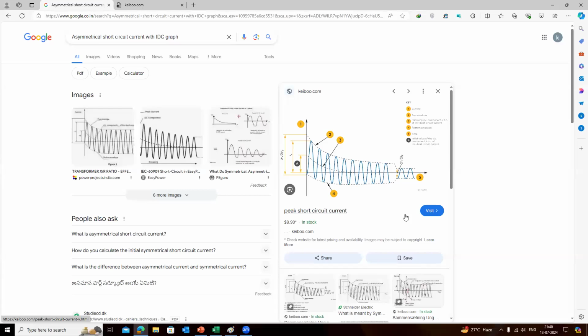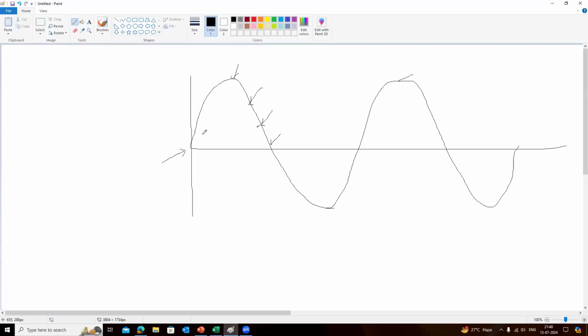All right. Now, coming back to this asymmetrical current, this is having the DC current as well as the peak value. All these things will change with respect to the instant at which the fault has occurred. Like if the fault happens here, the asymmetrical peak current will be different. Whereas if the fault happens here, again, all those currents will be different. But your steady state current, that IK, which settles after a few cycles, will be constant. Okay. Right.